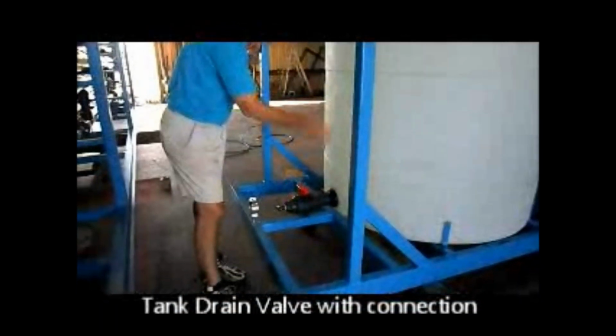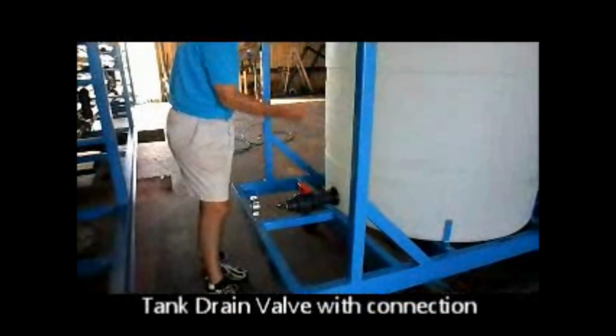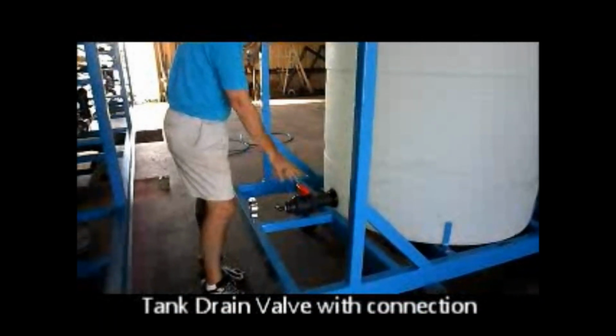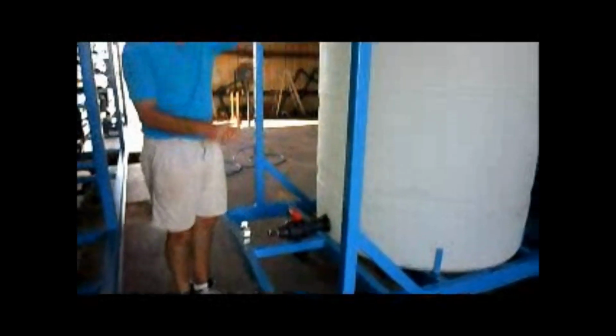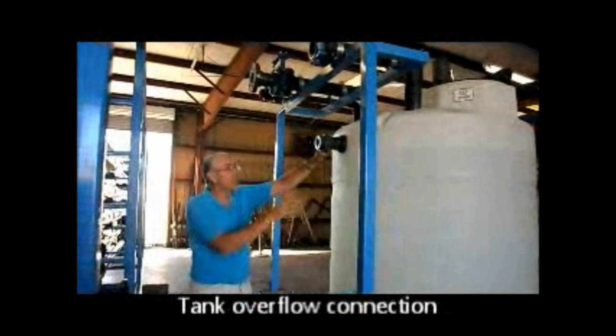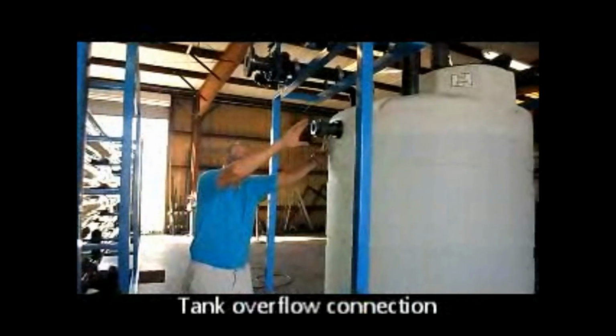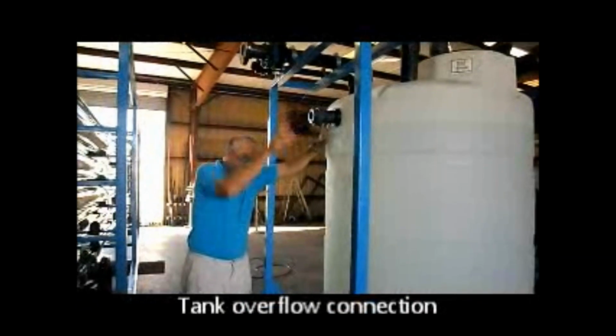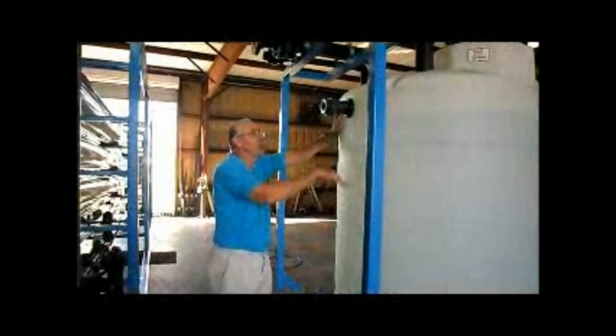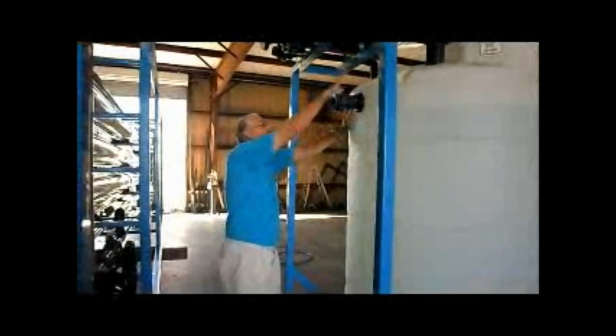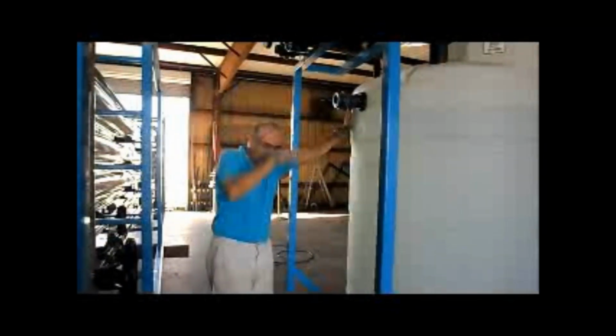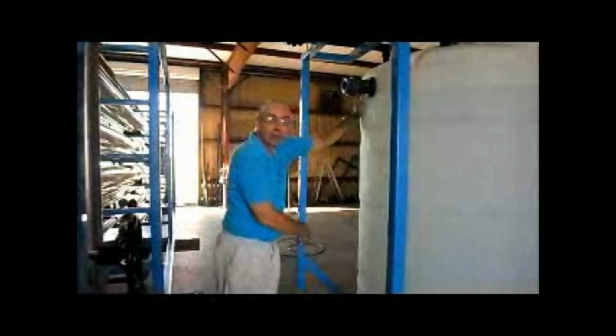The next one is the drain. If you want to drain the tank and get all the chemicals out, get all the water out, rinse it out, open this valve, drain it. There is an overflow. We took it off for the demonstration, but there's an overflow pipe which will be supplied with the system, which connects to this drain. So if for some reason the tank overflows, it will not go up the top. It will come out this pipe down to the drain and out.